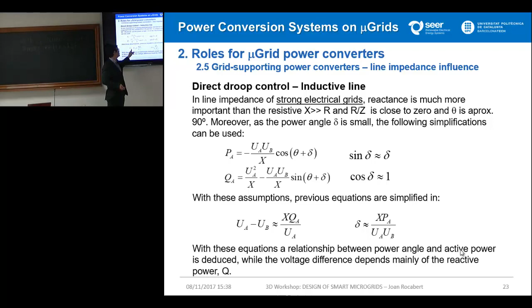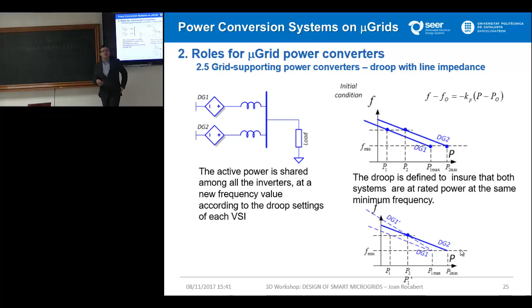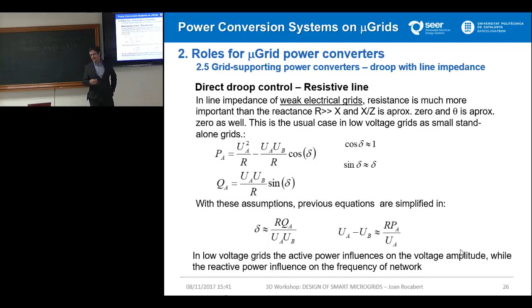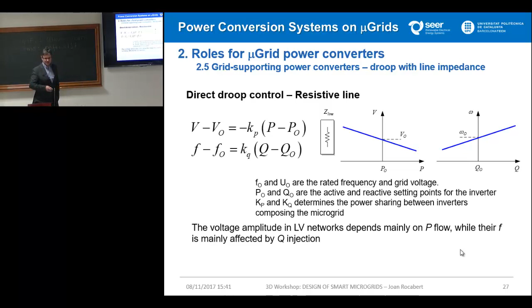And then the secondary control will come and say, okay, the new equilibrium point that you find is not the one that I want, and I want to restore again the frequency of the microgrid. So what the secondary control does is to move that constant of the droop equations to move the equilibrium point from that point to this one. Okay, impose a new equilibrium point at some specific frequency. The same occurs with a resistive line, okay, but in the opposite way. In the resistive one, the reactive power is related with the frequency, the voltage is related with the active power. And the droop lines change, okay?